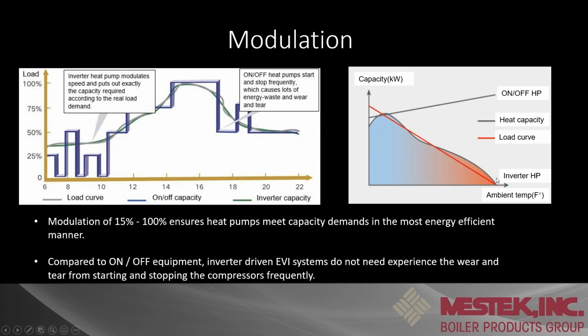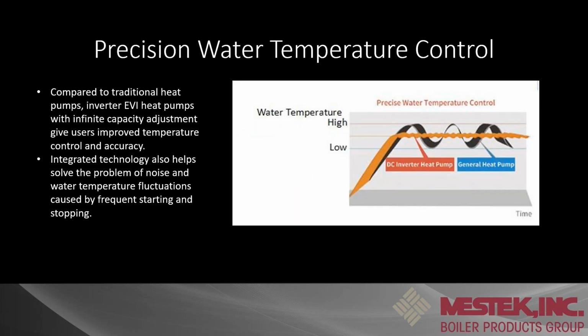Same thing on the right here. As we're looking at it, what's our capacity? We have a nice straight line versus a line that's up and down here. It's a huge benefit to have the inverter so we can match the load needed and maintain water temperature. Same thing here, it's just another type of chart. You're looking at your inverter heat pump and how our line is staying basically straight and we're maintaining temperatures. With a general on-off heat pump, you are definitely going to have fluctuations in water temp.